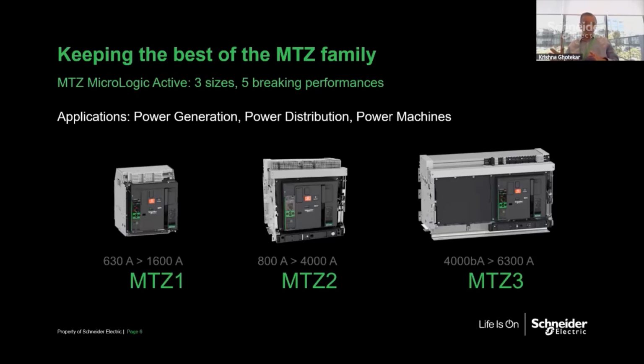The second one, 800 to 4000 ampere, like an NW 800 to 4000 ampere. Here it's MTZ2, so it's a size 2 breaker, 800 to 4000 ampere. And the bigger size breaker, like 4000B to 6300 ampere, like 4000B, 5000, 6300 amps, is size 3, MTZ3. So you have size 1, size 2, size 3. NT and NW go up to 4000 ampere, NW greater than 4000 ampere. So it's more simplified.